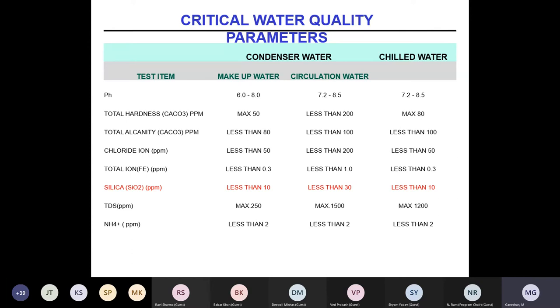record of this. In the same way, water is very, very important, especially in water-cooled chillers, both condenser water and chilled water. Whenever there is a customer, we have to tell the customer, sir, it is better to do this now. Otherwise, what will happen? There is no other alternative, at least do the descaling right in time. Or, if you can prevent it, we have many new things now which can stop scale from forming inside. Because any scale forming inside the condenser or the cooler, both, is going to cause inefficiency of the system.